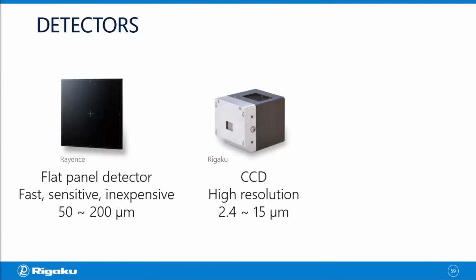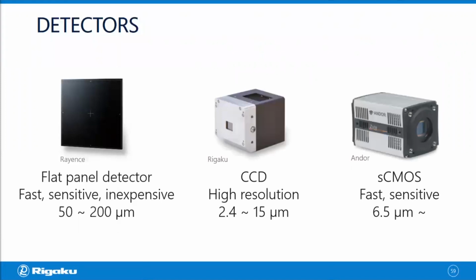CCDs are available with smaller pixel sizes, and they work better for high-resolution imaging. Nowadays, the CMOS, or I should say SCMOS detectors, they are available with pretty small pixel size, like this one from Andor comes in 6.5 micron pixel size. And by using those SCMOS detectors, you're not compromising on the resolution that much, but you can make the scans quite a bit faster. So for faster scan, high resolution scan, the SCMOS detectors would work better than the CCD. And those are the three major categories of detectors.